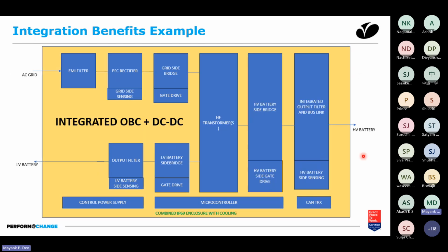So the combined block diagram of this integrated subsystem will look something like this. You will have only one power supply, one micro, one communication module, an integrated output filter and bus link on the HV side, with only one module for HV side sensing of voltage and current, the HV battery side bridge, which is probably some form of integration of power devices and gate drive, and probably an integrated set of magnetics. The EMI filter on the AC side, the PFC rectifier, and the grid side bridge will remain as is. Similarly, the LV battery side bridge, gate drive, and output filter will also remain as is. But together, this results in significant synergy and significant savings when it comes to overall system level performance.